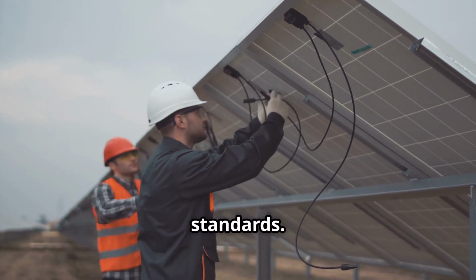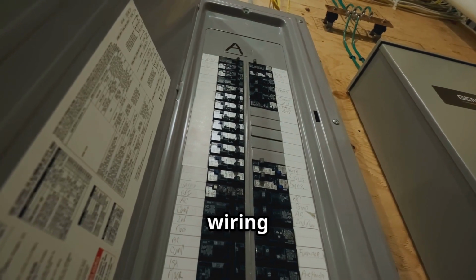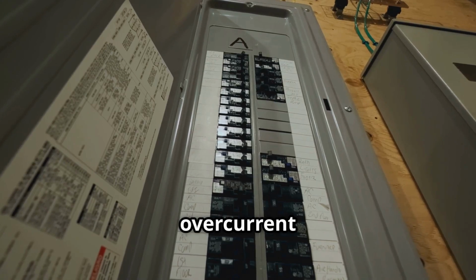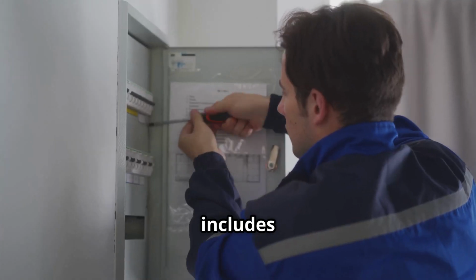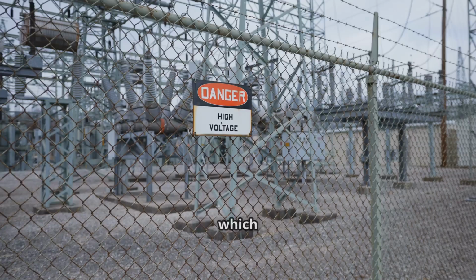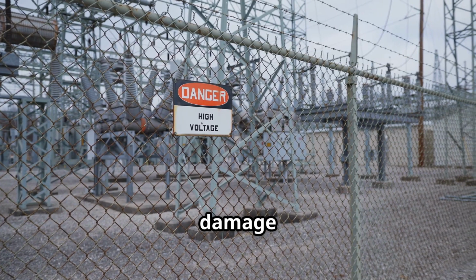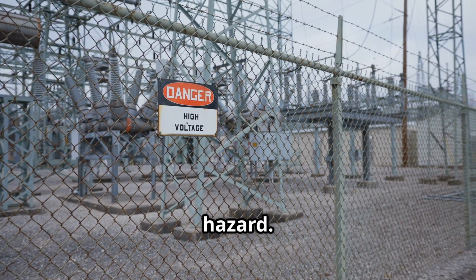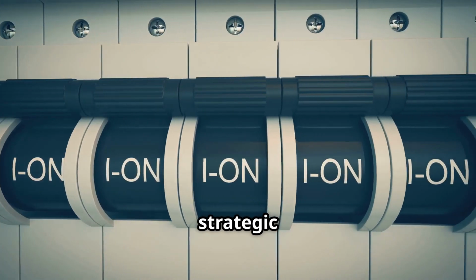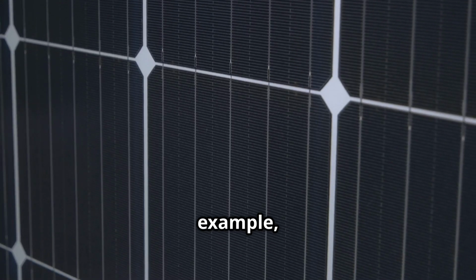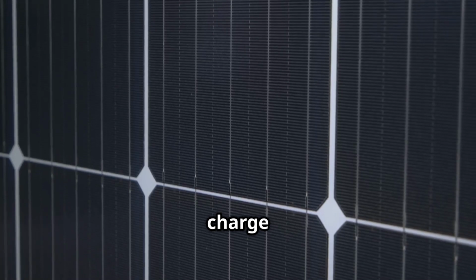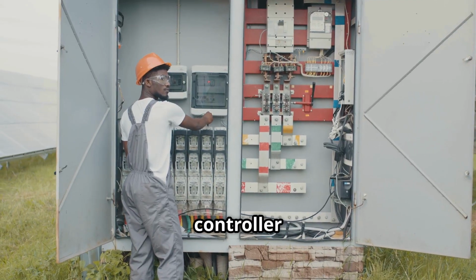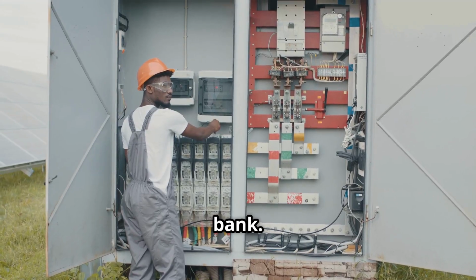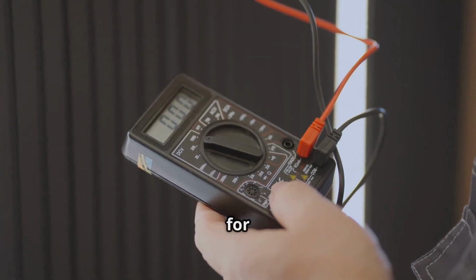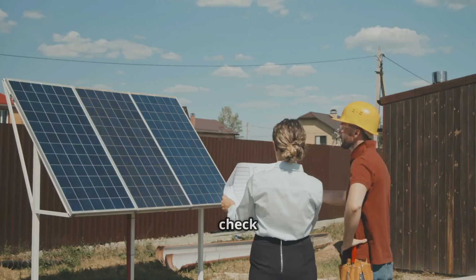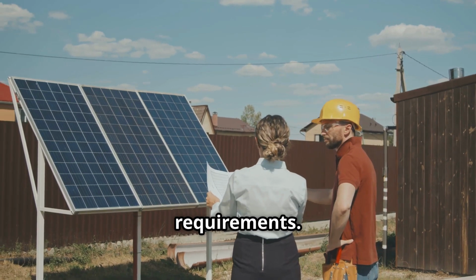A key component of a safe wiring configuration is the use of overcurrent protection. This includes fuses and circuit breakers, which prevent excessive currents that could damage your equipment or create a fire hazard. Position fuses at strategic points, for example, between the solar panels and the charge controller, and between the charge controller and the battery bank. Make sure these protective devices are rated for the current levels in your system and check local codes for any specific requirements.